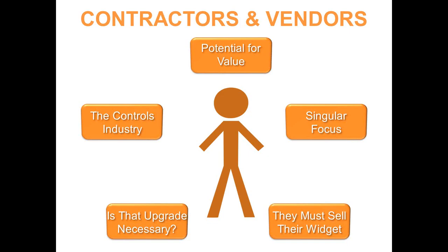So one of the questions we often ask ourselves and we ask building engineers to ask themselves is, is that upgrade really necessary? In other words, does the system actually provide any additional value by upgrading the software packages? Or would calibration of thermostats and all the other devices in the building that operate equipment and systems be a better route to go? And by and large, considerably less expensive. So we need to understand that contractors and vendors will have a singular focus.